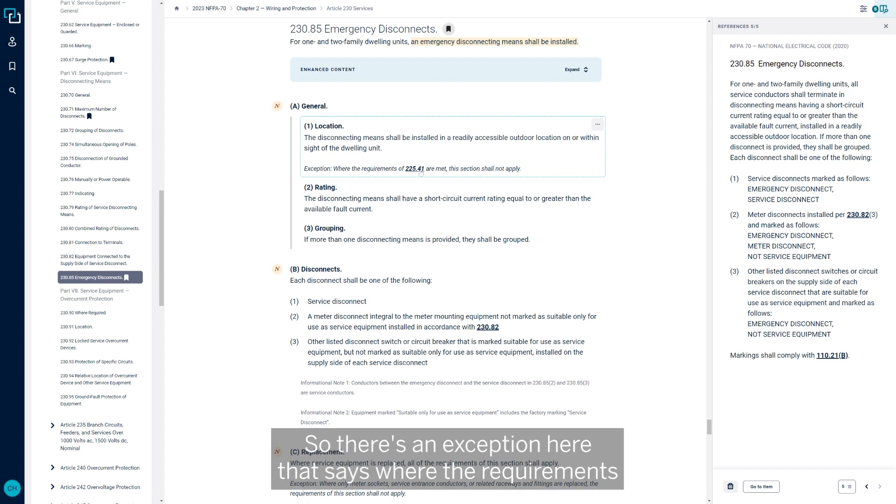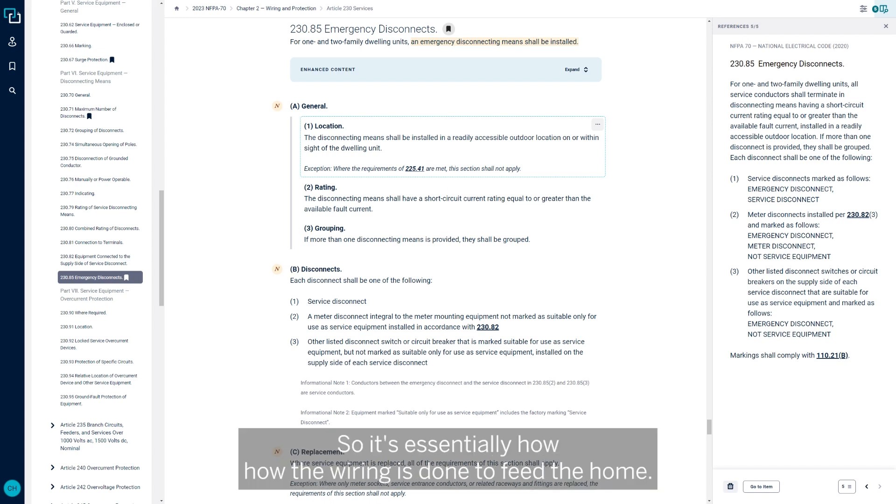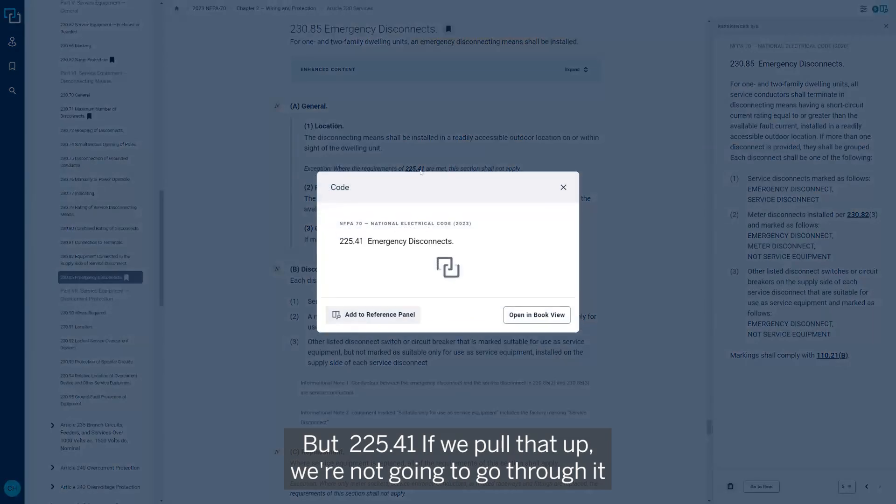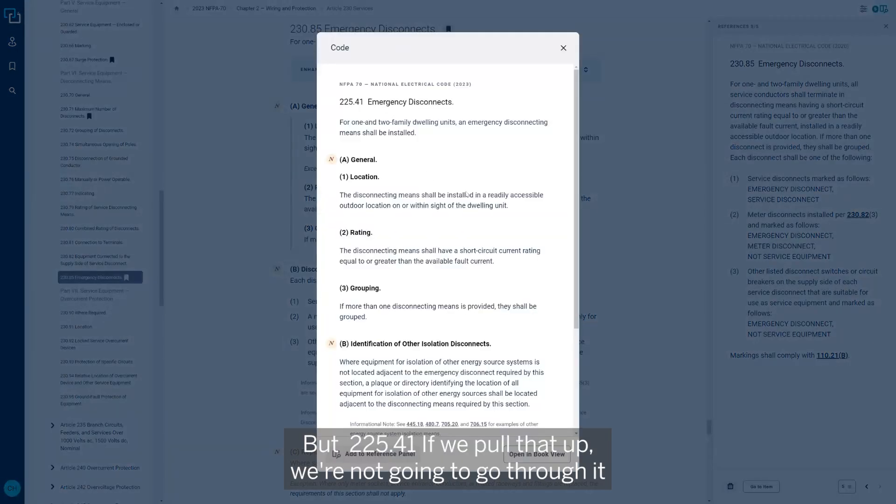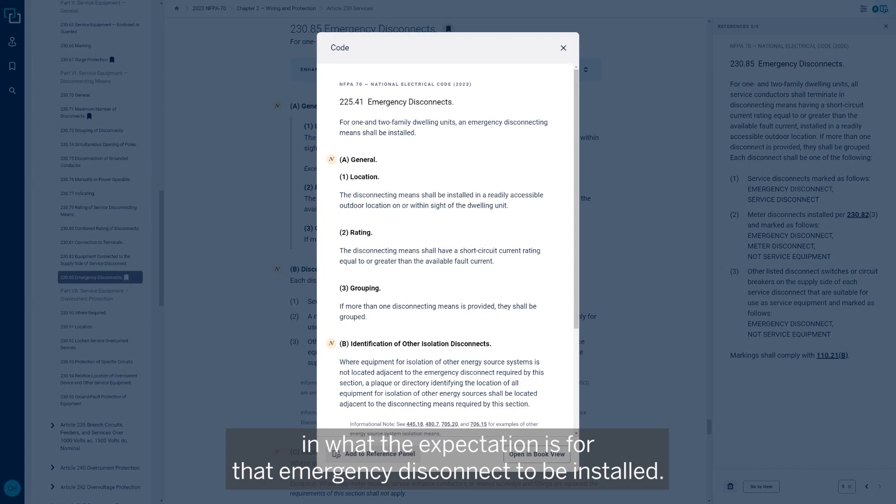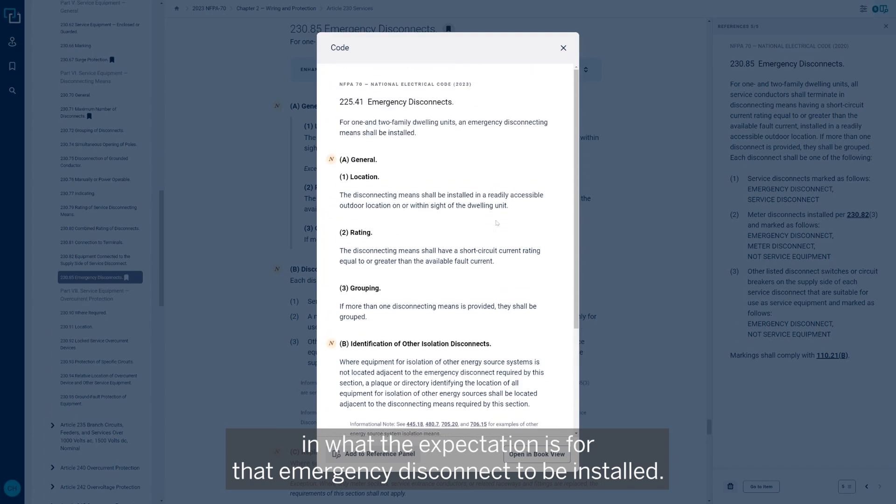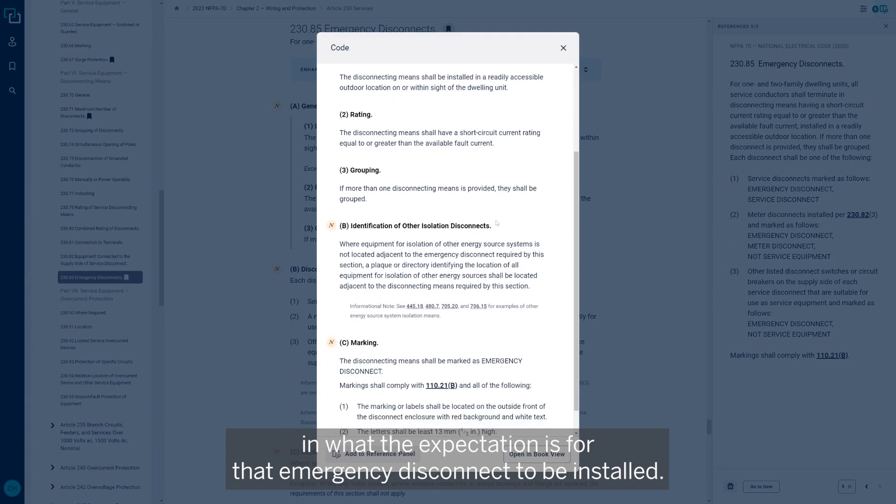If we look at part A of 230-85, the first thing is the location. The disconnecting means shall be installed in a readily accessible location outdoors on or within sight of the dwelling unit. Now that's pretty clear. But in some scenarios, we may have a situation where the main disconnect may be located at a pedestal out at the road and then feed the disconnect.